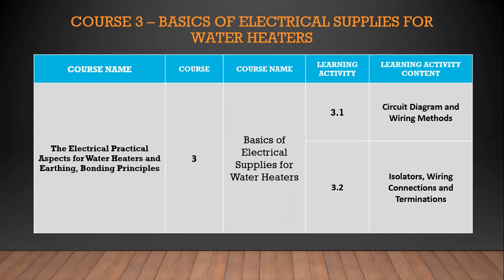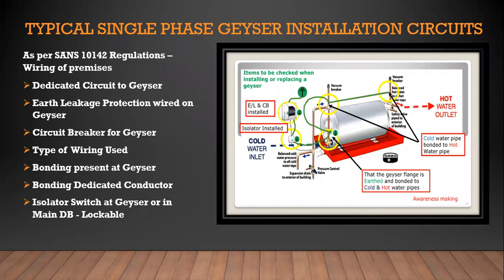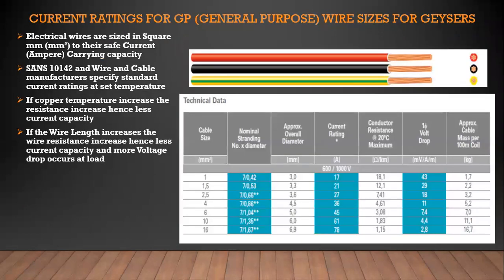We're looking at the basic supplies and circuit diagram and the wiring methods, isolators, wiring connections, and terminations. In this course 3, I will show you a typical single-phase geyser installation circuit. I think you all know how that looks, but I'll go into detail on what a circuit breaker is and the type of wiring used. People use different types of wiring to supply these geysers: surfix, twin and flat earth, general purpose wire with conduit. I discuss all these methods and obviously the isolator switches. I look at current ratings for general purpose wire sizes for geysers. So you can look at an installation to determine if the wire size is actually correct, and you will not put too much current onto this wire for a particular installation.